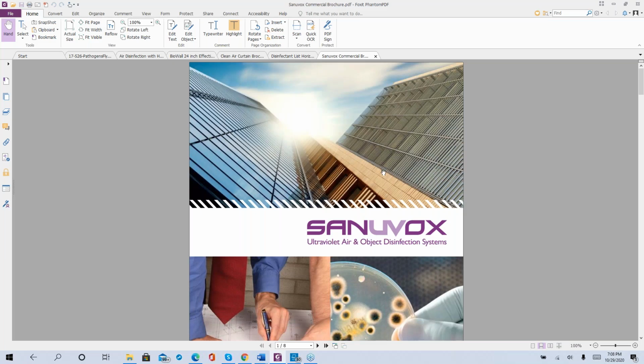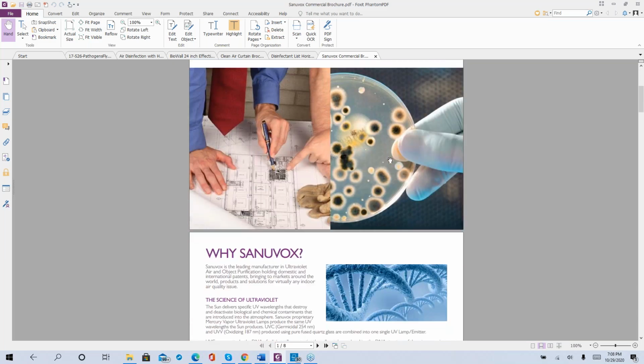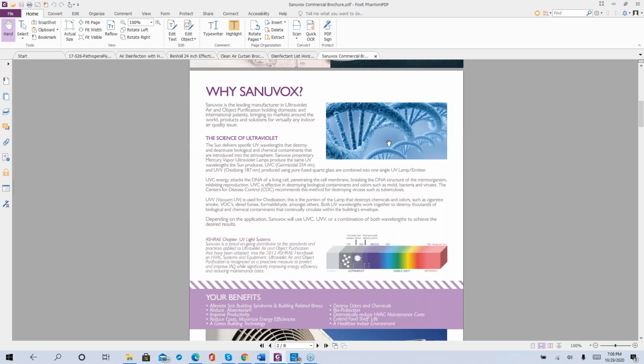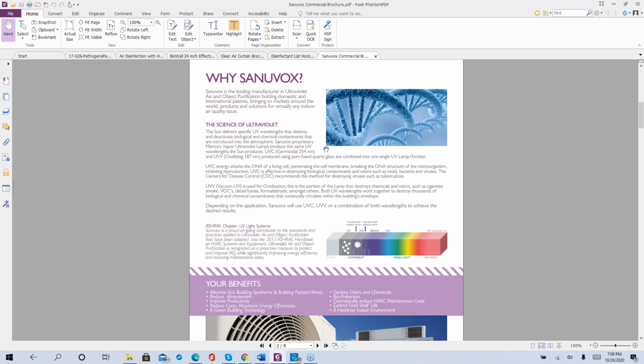So this is Sanuvox, and Sanuvox is probably the better manufacturer that we have looked at. But before we talk about the commercial and the Sanuvox, at least now you've got something to look at. Everybody was listening to residential use of UV, also called stick lights. Every truck had some, and you were expected to sell them as add-ons, increasing the profit margin. They are mounted perpendicular to the airstream and treat a very small portion of the airflow, maybe only an inch around the diameter and along the length.